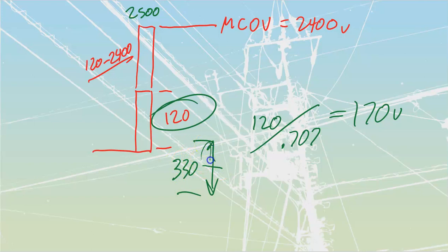They're just looking at how high my sine wave is going to go above each one of these. In reality, it's going to be a little bit higher than that. Yes, we are above 170, but that 330 rating is just a standardization. It's like how we say 115, 230, or 125, 250, or 120, 240. We're referring to the same thing. It's a nominal system type.